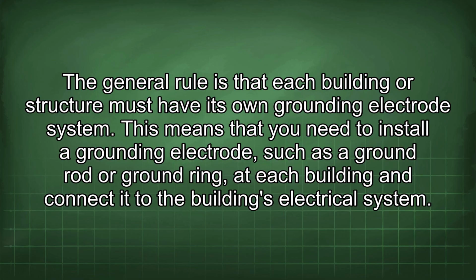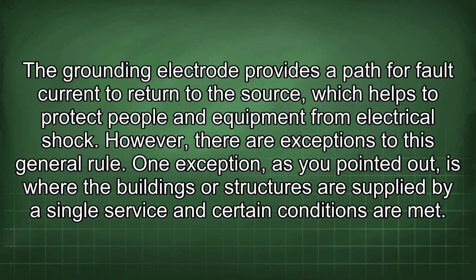This means that you need to install a grounding electrode, such as a ground rod or ground ring, at each building and connect it to the building's electrical system. The grounding electrode provides a path for fault current to return to the source, which helps to protect people and equipment from electrical shock. However, there are exceptions to this general rule.